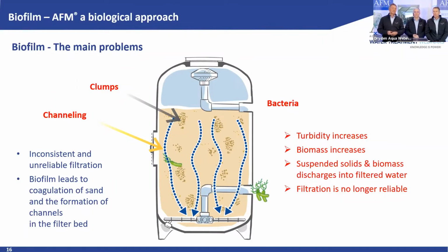And why is this? This is because of these autotroph bacteria. Because when they move into the system, they produce the food source for the heterotrophs. And this is when this biofilm problem starts to become a lot more dramatic. They are not doubling every 30 minutes, but every 10 to 12 days. This is why it takes a lot longer to move them in. But if they are in, it becomes very dynamic. The big issue is you get more bacteria out at the end than you get in. And that can be a big problem in other processes downstream.